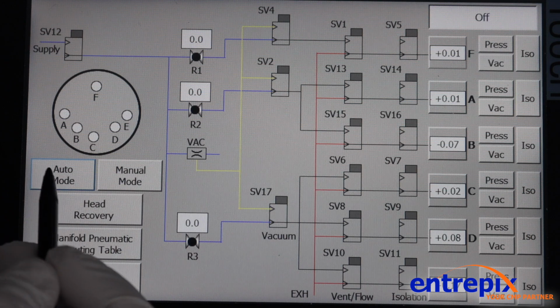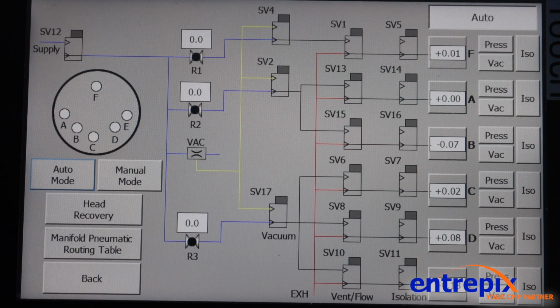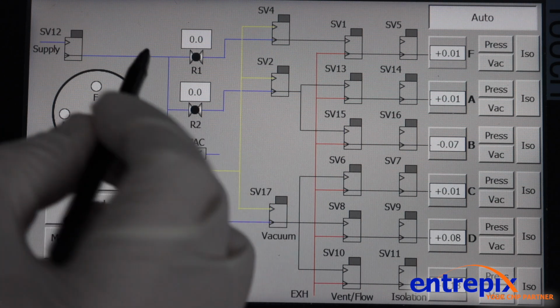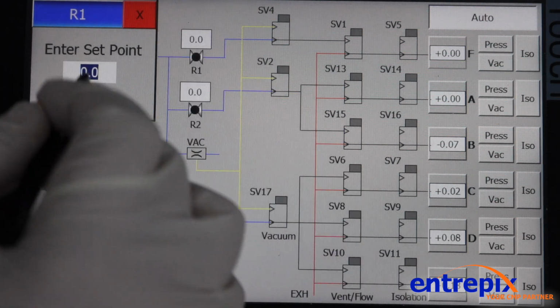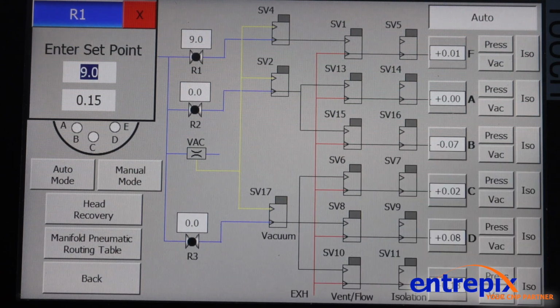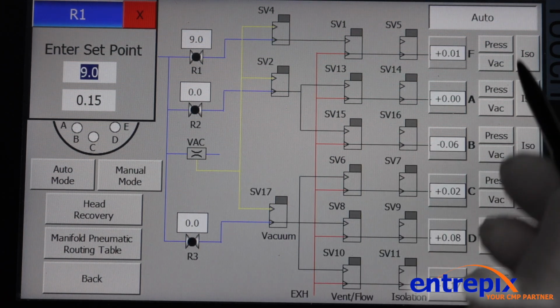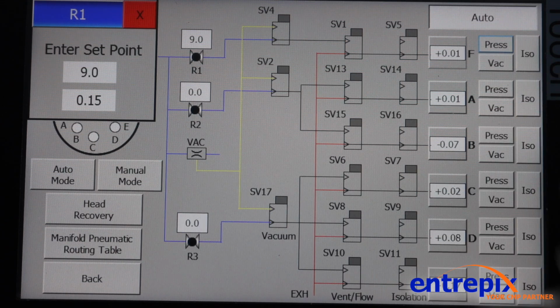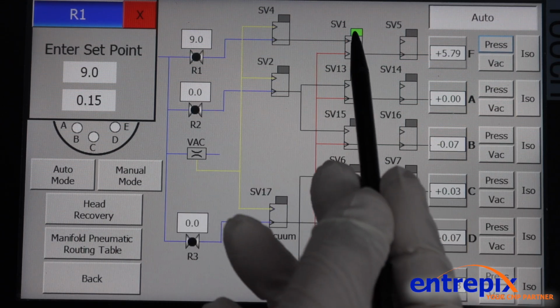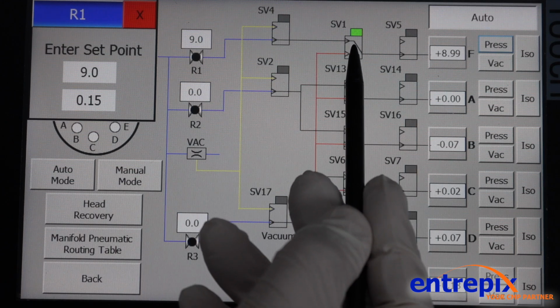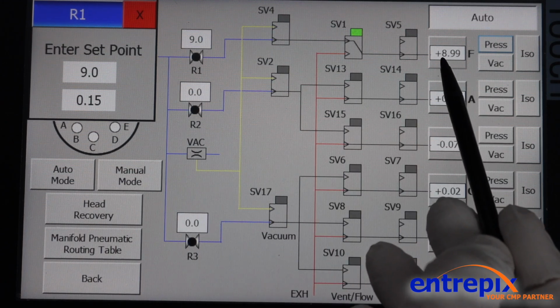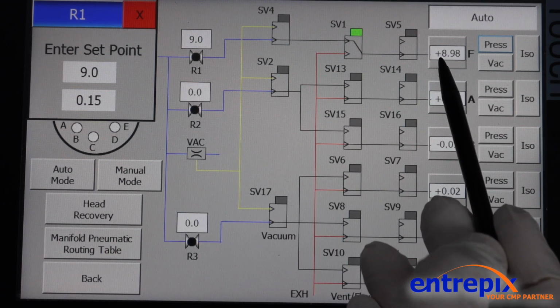Start by depressing the auto mode button. This will make all of the diagnostics on the screen alive. Next, select the regulator and put in a value. For this demonstration, we'll select 9 psi. Next, press pressure. You will see in real time the valve come live that's supplying the pressure and the indicator from the transducer feedback that we are at approximately 9 psi.